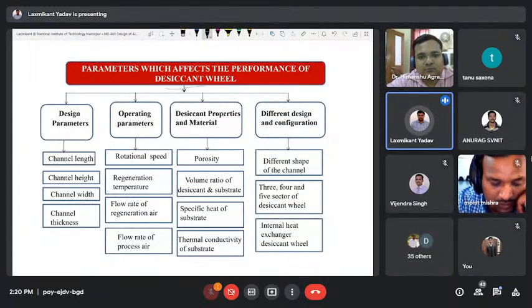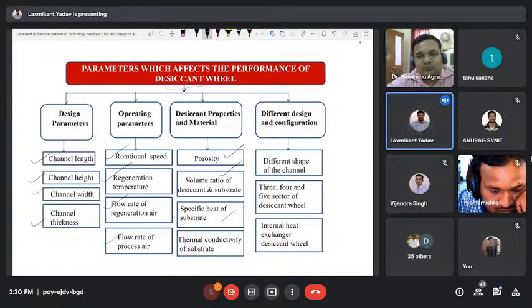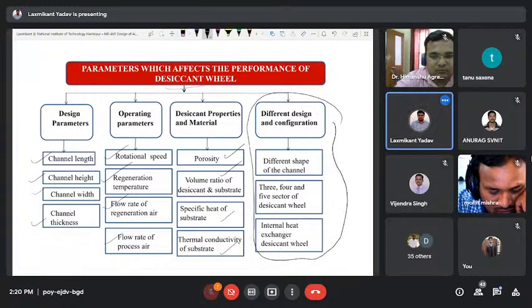So different design parameters of the desiccant wheel are the channel length, channel height, channel width, and channel thickness. Similarly, the operating parameters of the desiccant wheel are rotational speed, regeneration temperature, flow rate, and desiccant material properties. These are the porosity, structure of the desiccant, specific heat, and thermal conductivity. So these are the emerging areas where I have done my work. Also my MTech students and PhD students are working on different designs and configurations of the desiccant wheel. So these are the 3, 4, 5 sector desiccant wheel and the internal heat exchanger desiccant wheel.